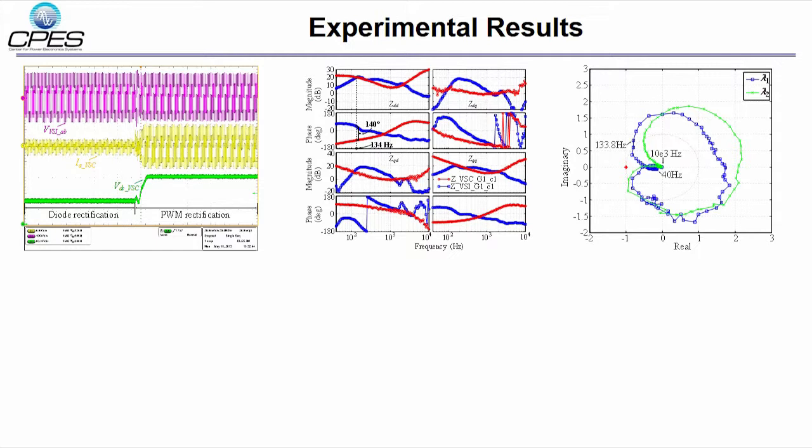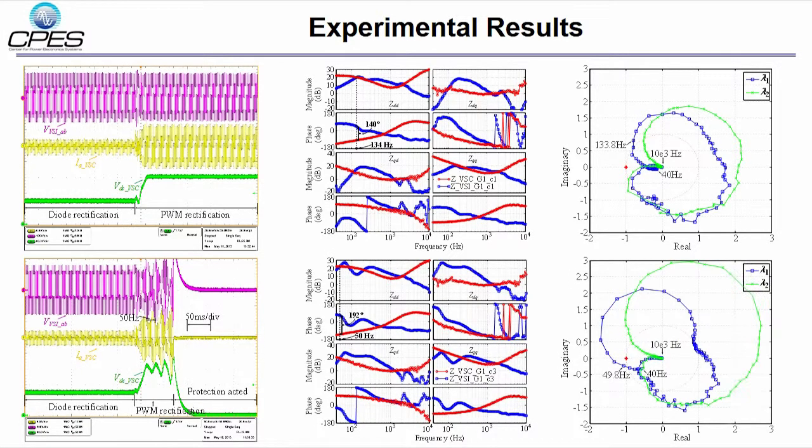Then, in the second experiment, the VSI output voltage control loop bandwidth is reduced. When the load converter is started, the system runs into unstable condition. The impedance measurement results as well as the generalized Nyquist plot show the same conclusion.